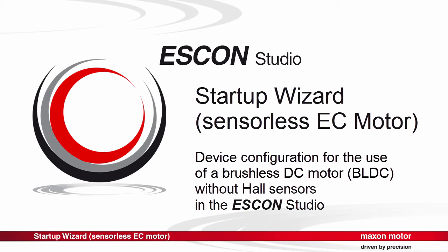This tutorial describes the minimum configuration of the ESCON Servo Controller's sensorless module. The setup is for a brushless DC motor without Hall sensors. The startup wizard, a tool from the ESCON Studio, allows to configure the servo controller with just a few steps.